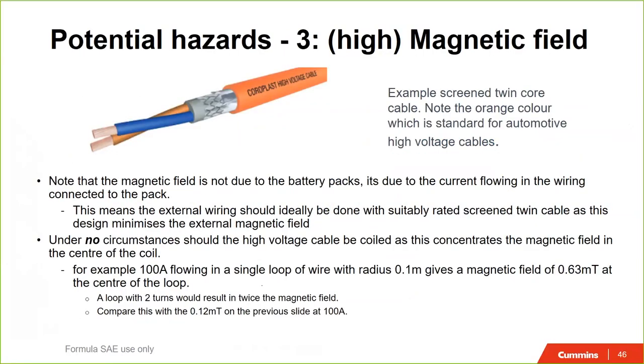How do we mitigate against high magnetic fields? Screened twin core cables, twisted pair cables, are a great way to reduce the magnetic field. The magnetic field itself, as I said, is not due to the battery pack, it's due to the current flowing in the wiring. Again, this means that your external wiring should be done with the correct cable. Don't just use any old scraps of cable you find around the workshop. An interesting one here is that in no circumstances should the HV cable ever be coiled up. Cut cables to length and make them fit. If you coil cables up because it's easier than putting a new connector on the end, you get twice the magnetic field per loop that you put in that cable.